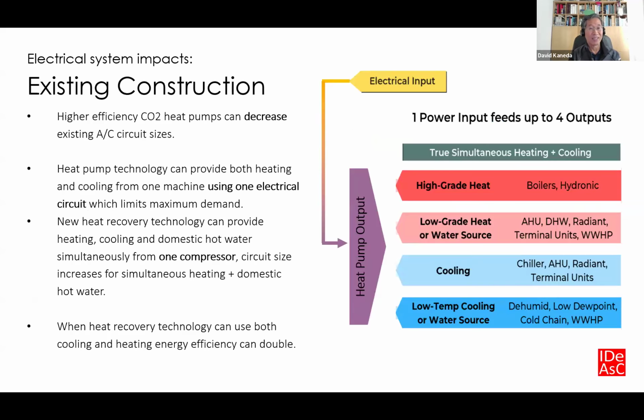The last thing is CO2 heat pumps can decrease circuit sizes, as Rami was talking about. With this technology, one device can do multiple things like heating, cooling, and domestic hot water. Using one compressor and one circuit can reduce the demand, saving you both on energy use and on circuits.